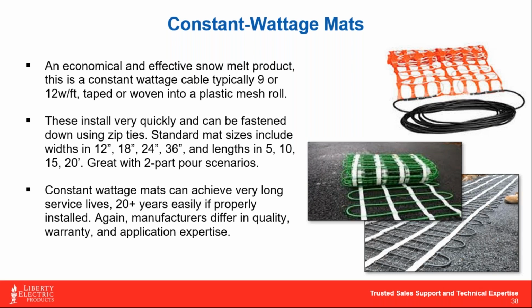Typically what you're doing is putting your wiring leads to one side of the sidewalk, then extending those leads all the way back into the building or wherever the power source is going to be. We do not want to make splices out in the field with this particular product. We've seen it happen for years where an electrician or installer can talk as much as they want about how well watertight fittings or wire nuts might work underground, but we've seen them burn up. I think you're asking for trouble making terminations in a Quazite box underground. If you have to, at least make sure the junction box where you're making wiring terminations is well above grade and can't get saturated. Keep the moisture out of the connection.